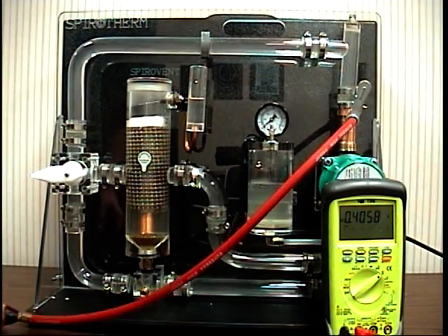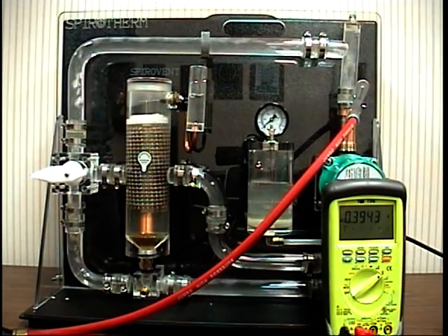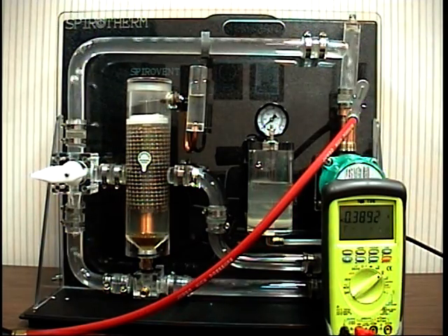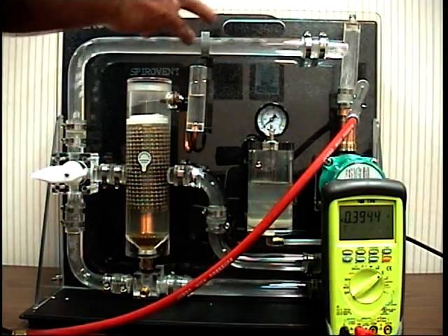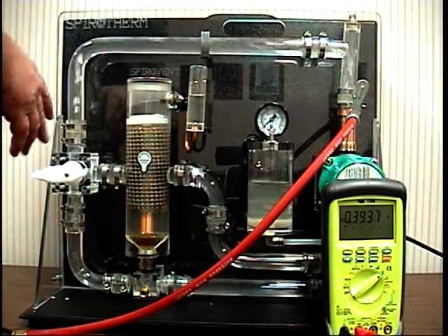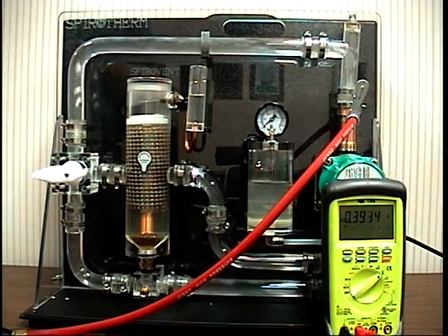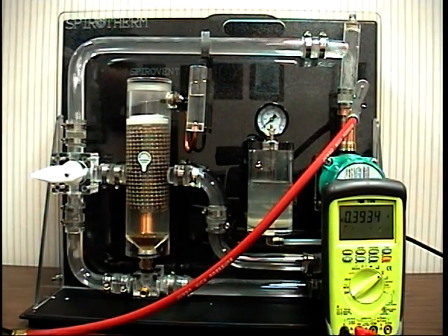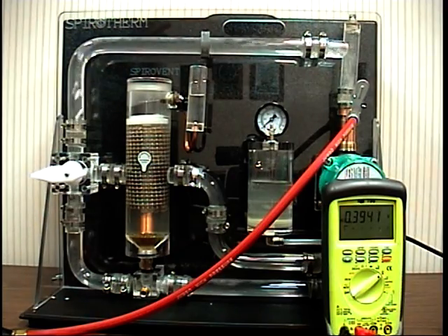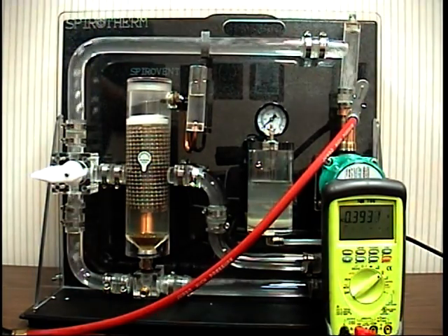Basically, I'm going to go ahead and inject a little air into the system, and immediately you can see what happens. The system becomes very noisy. The velocity of the water is erratic, and there's also a lot less heat transfer. Let that circulate for a minute, and you can see some free air bubbles sitting at the top of the system now.